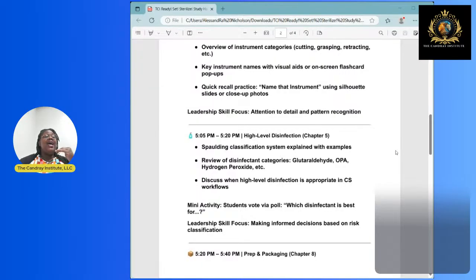Anything like that has to be high-level disinfected. That's going to be a chemical sterilization. Or excuse me, see how I did it? I just slipped up. I said chemical sterilization. That's not right, because sterilization means everything is dead, and high-level disinfection is not everything dead. It's high-level disinfection, chemical disinfection. And then the last one was critical items. Critical items are the items that are going into your sterile body cavities or your vascular systems. That's basically all your surgical instruments. And those absolutely have to be sterile, free of microbes.